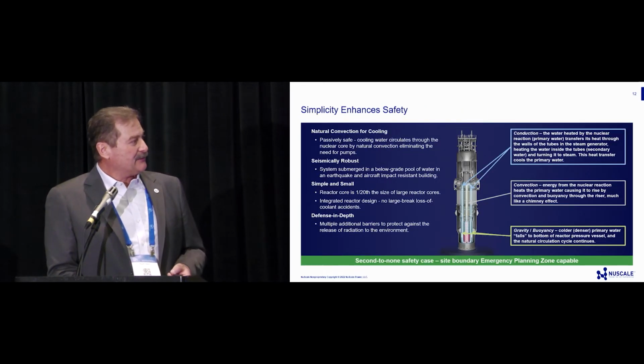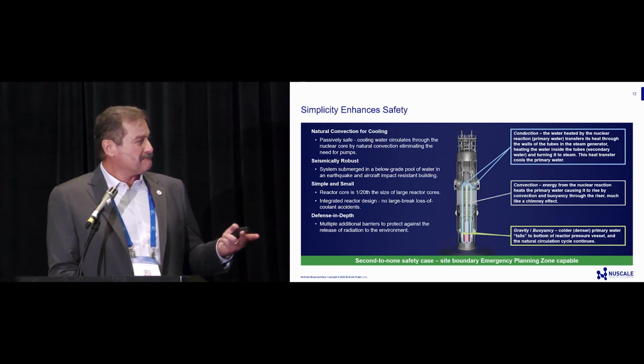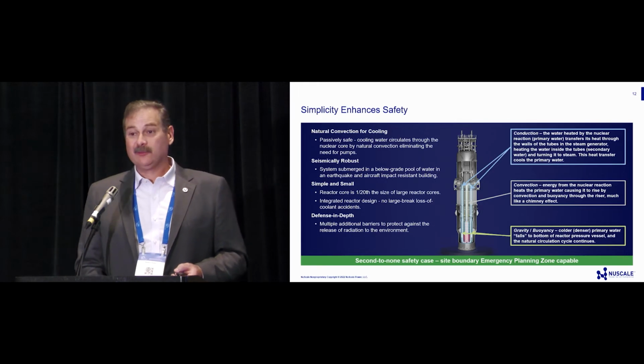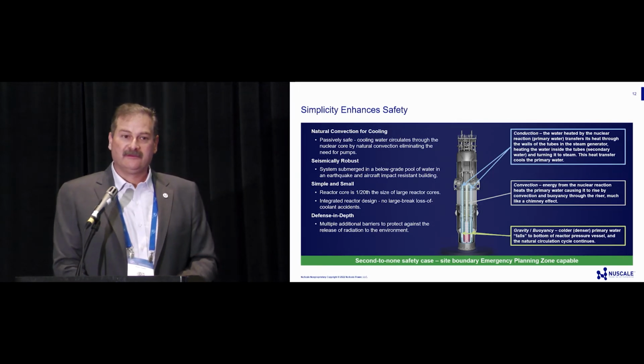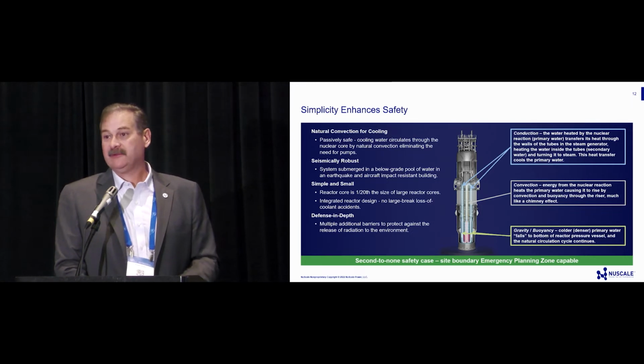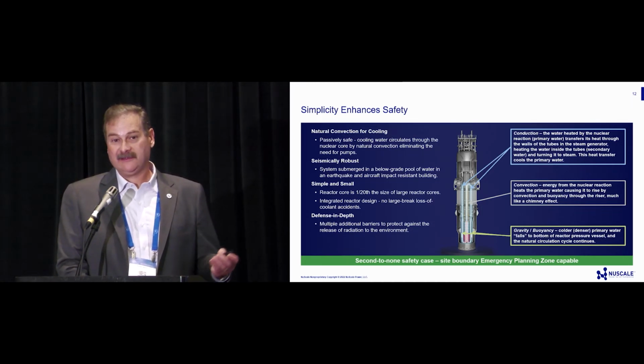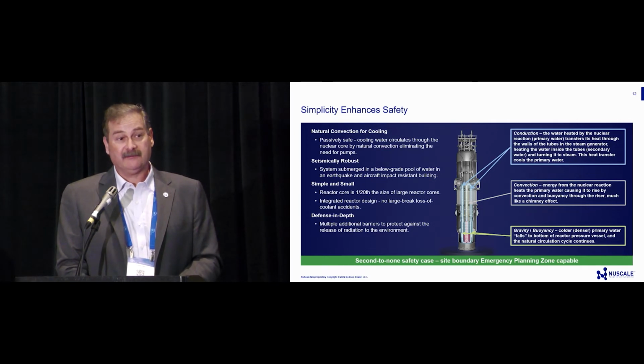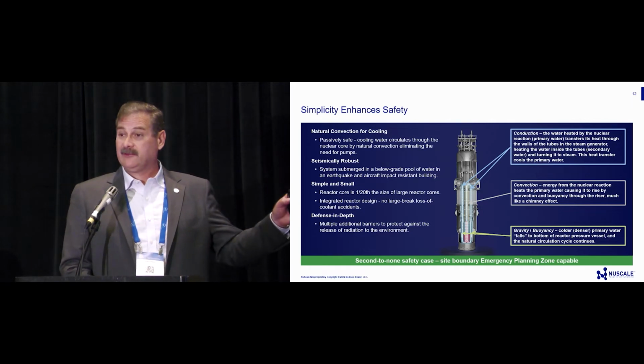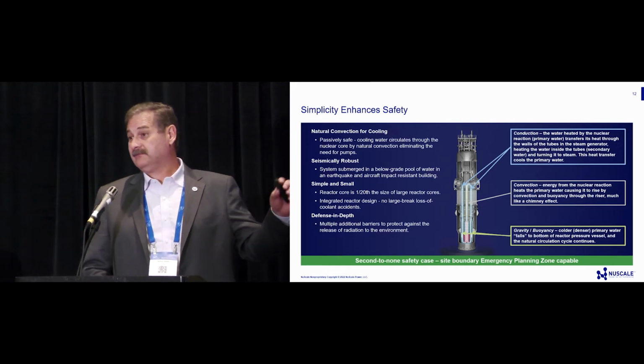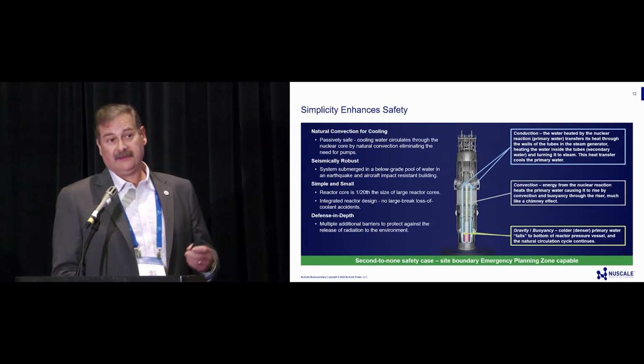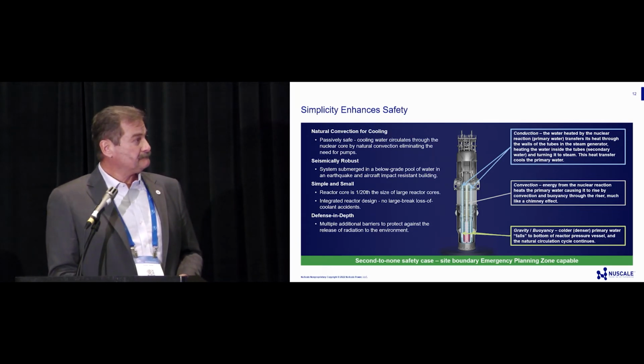Natural convection for cooling, seismically robust, simple and small. The reactor core is about 1/20th of the size. Currently right now we're using what would be Framatome, or originally Westinghouse, 17 by 17 fuel assemblies, just like virtually all the pressurized water reactors in the United States use. It's virtually the same fuel. The only thing different about it is about half the height of a conventional fuel assembly, but the construction is the same.